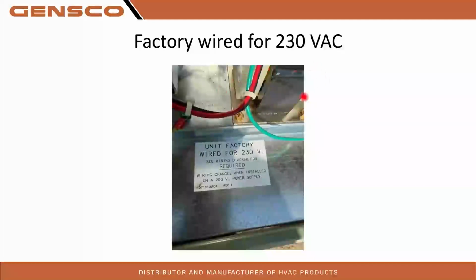Factory wired for 230, unless ordered differently. So keep that in mind. The unit is factory wired for 230. You might have to change your transformer taps to get a good 24-volt output. We have had that happen a few times in the field, where we get calls saying it's not working because we don't have a good 24-volt.